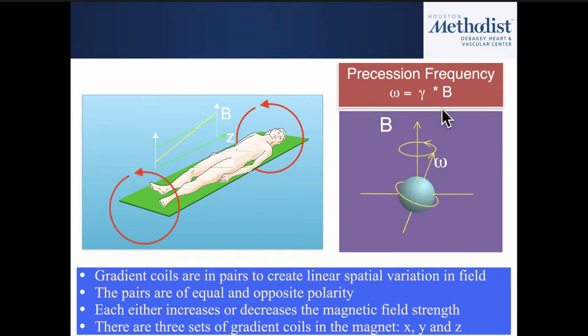So when I apply a radio frequency pulse, I can apply a pulse at a set frequency so that only those protons get excited. If I'm interested in imaging a slice right at isocenter, then I would send in a radio frequency pulse that's exactly at 64 megahertz. If I want to go a little bit more towards the head, I would use a radio frequency pulse that's a little bit higher. Now, we don't have to figure this out. The scanner does all of this for you automatically once you prescribe a line to say, I want to image at this slice location. So again, that's using the gradients, and it's relying upon the Larmor equation, which basically says that the protons spin at a rate which is directly related to the magnetic field.